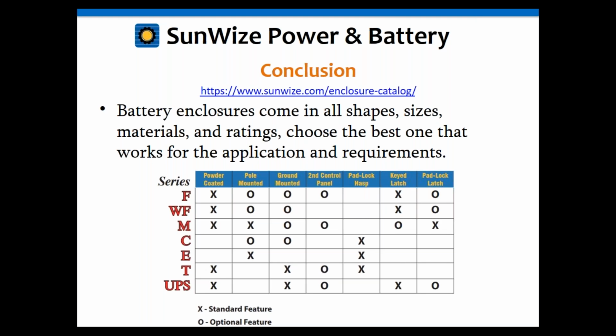A couple reasons for that: one, it reduces cost, which is always nice since people like to do things cost effectively, so having fewer enclosures is usually more cost effective. The other reason is that if you're using a charge controller with an internal built-in temperature sensor, you want to keep that sensor as close to the batteries as possible. It also keeps your cable runs shorter between the actual devices, meaning less losses in the wire between the batteries, the charge controller, and other devices. So there are good reasons for that.